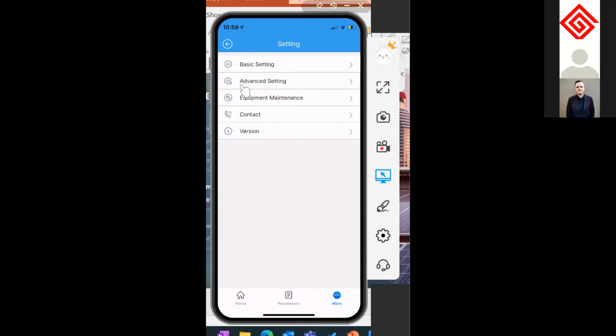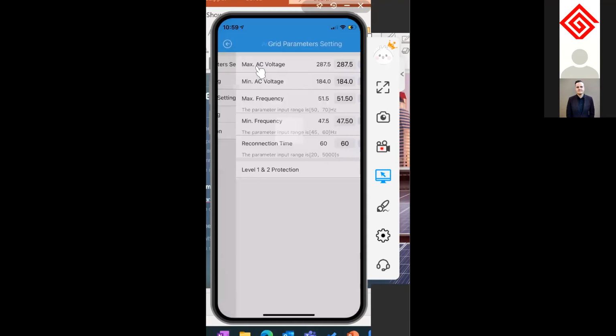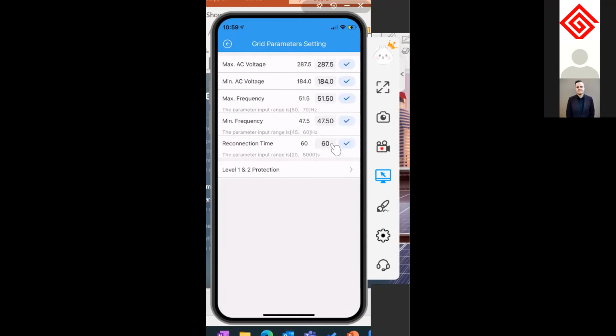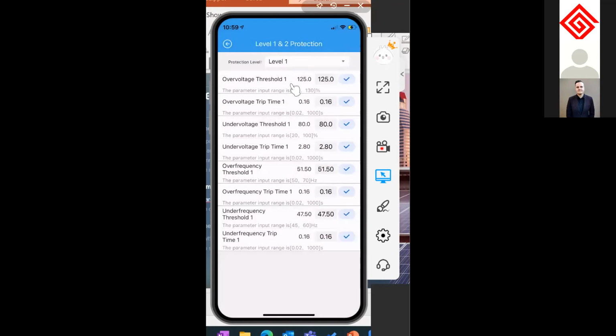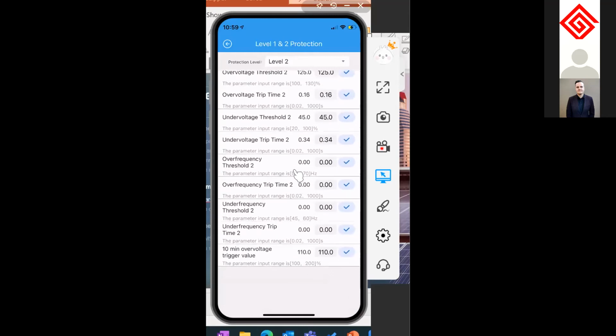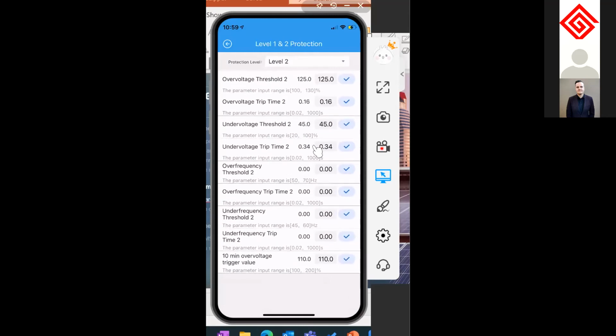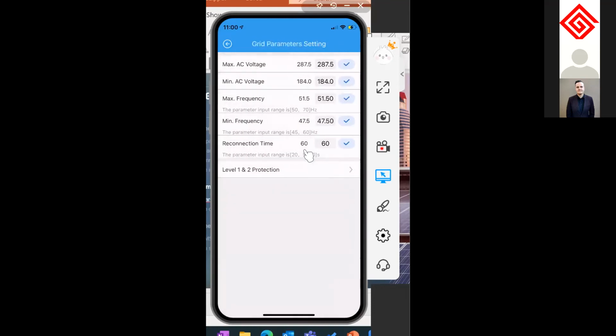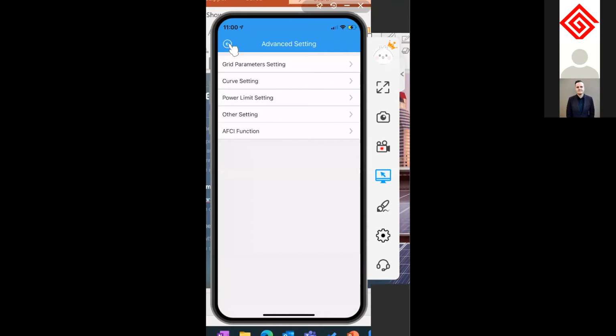But in case there are some extra things that you need to do, then you can click here on advanced settings. And then here you can change the grid parameters to a specific value if you want. You also have level 1 and 2 protection. Here you can change some more parameters, and you can even change here to level 2 to get some additional. However, please keep in mind, do not change these if you don't know what they do. Back, we have then the curve settings here, and then you can set specific QU curve, or this is the power factor here, for example.